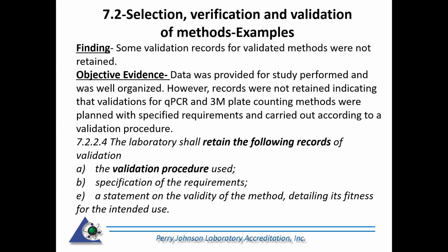Some validation records for validated methods were not retained. I just talked about records. In this example, data was provided for a study performed and was well organized. However, records were not retained indicating that validations for qPCR and 3M plate counting methods were planned with specified requirements and carried out according to a validation procedure. So here is a citing under 7.2.2.4, where we require the laboratory to retain records in accordance with their validation procedure.